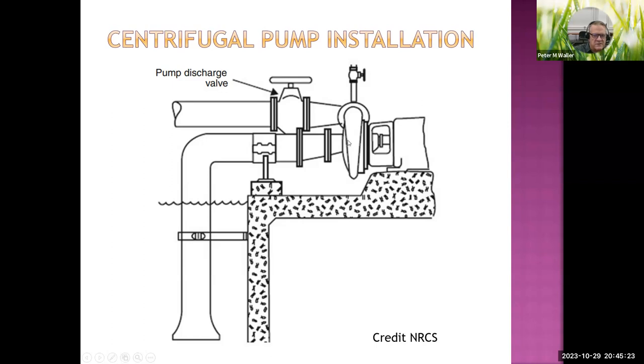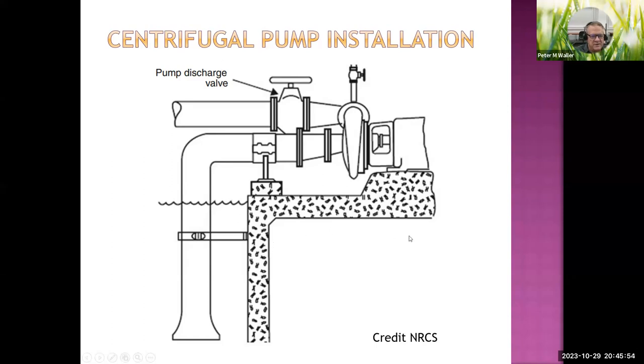If the pump is above the reservoir, a priming pump and priming valve are needed to evacuate air and draw water up into the impeller before starting. Always place the pump below the water level if possible to avoid priming issues and loss of prime. If the pump must sit above the reservoir, you need the priming system. Always start a pump against a closed discharge valve — then slowly open it. Never leave the discharge valve closed more than 30 seconds, as pumps are water-cooled and will overheat.